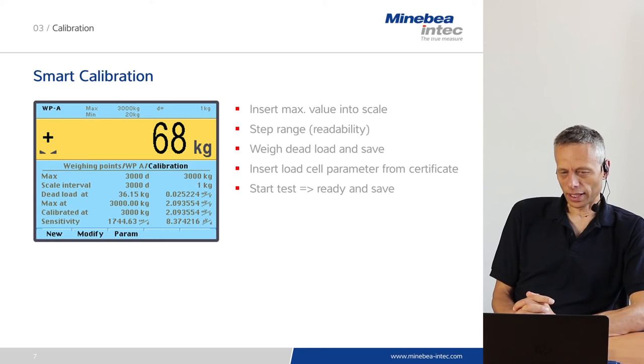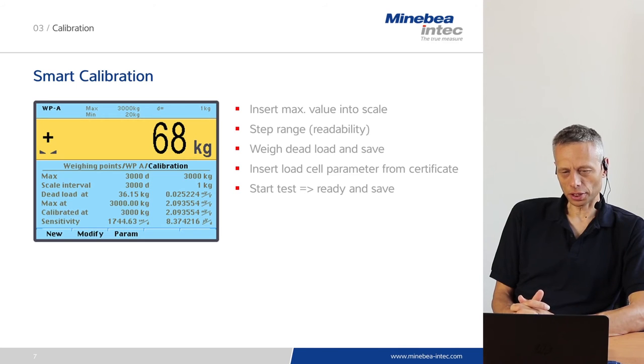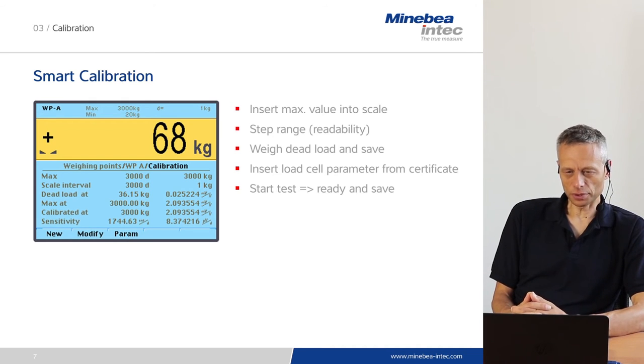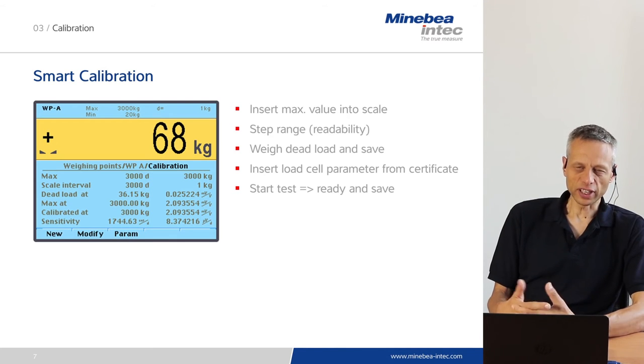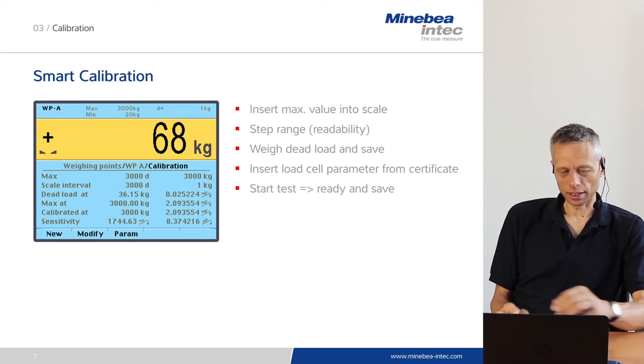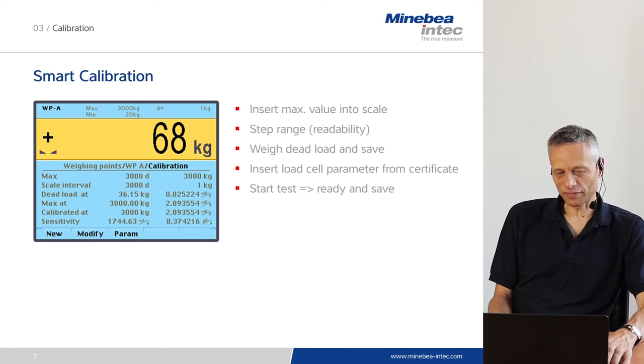In the next step we will show you a smart calibration procedure based on calibration data from load cell certificates, where we insert the maximum value into the scale and other parameters to finally achieve a full scale span value.